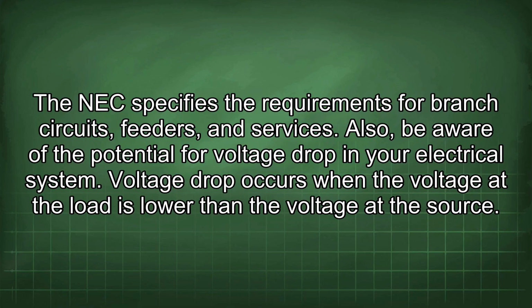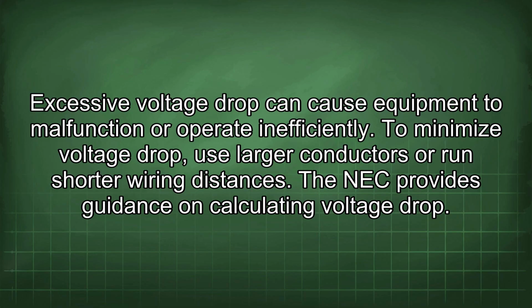Also, be aware of the potential for voltage drop in your electrical system. Voltage drop occurs when the voltage at the load is lower than the voltage at the source. Excessive voltage drop can cause equipment to malfunction or operate inefficiently. To minimize voltage drop, use larger conductors or run shorter wiring distances. The NEC provides guidance on calculating voltage drop.